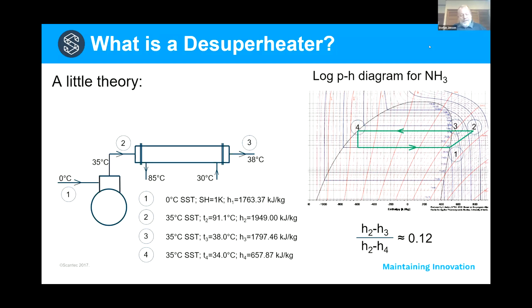Now it's important to note here that in an ammonia plant, we can only recover roughly 12% of the entire condenser heat rejection. This is assuming we have reciprocating compressors. If we have other types of compressors like screw compressors, that 12% is less. More about that later. This is what I've tried to show with that little formula down the bottom. In this case, we can recover high-grade heat to the tune of 12% of the total condenser heat rejection that comes out of that compressor, or multiple compressors operating in parallel.